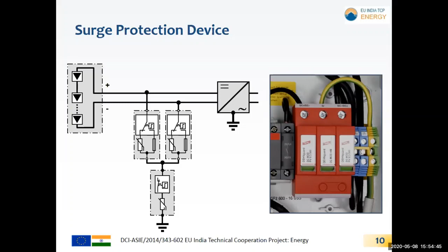Here you can see positive, negative, and earth connections. If it's an AC SPD, it's phase, neutral, and earth; if it's a DC SPD, it's positive, negative, and earth. This is the fuse with a green indication, which turns red when it blows out, and then we have to replace the fuse. This is the connection of the SPD and how it works.